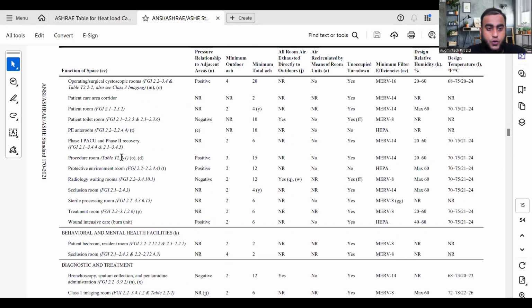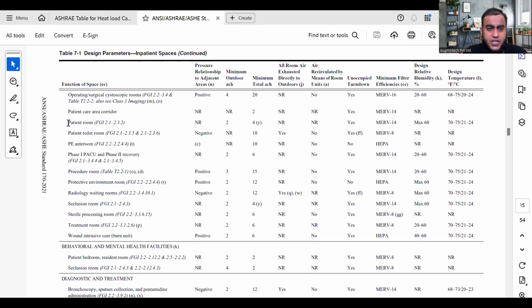Okay, same way when you scroll down, suppose if you are designing for a patient room, for example, patient room. So in patient room, pressure relationship to adjacent area is not required. Okay, so that is why it is given not required. So don't worry. Minimum total ACH is given 4. Okay, all room air exhausted directly to outdoor is not required here. Here we can use that air again. Okay, so don't need to exhaust all 100% air in patient room.